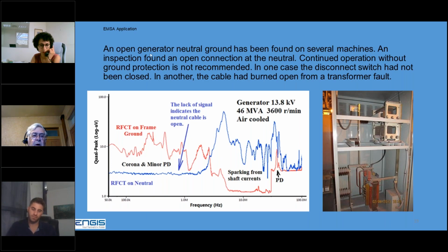This one, an open generator neutral ground, was found on several machines. An inspection found the connection at the neutral open. Of course, continued operation without this ground protection is not recommended. In one case, we found the disconnect switch going to the grounding transformer had not been closed after an outage. In another instance, a cable burned open from a recent transformer fault.